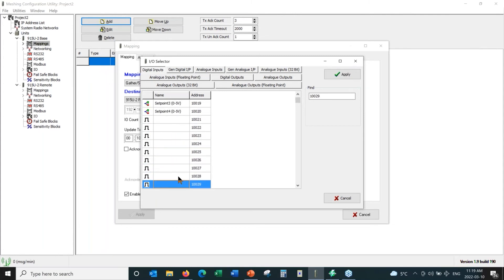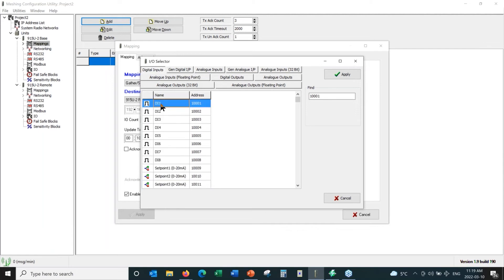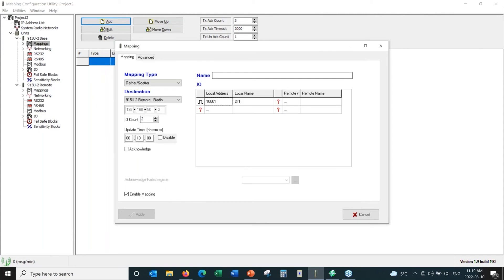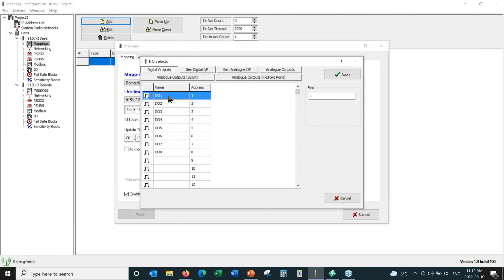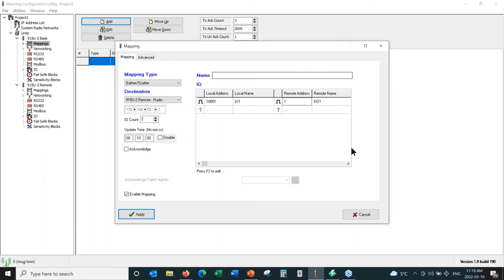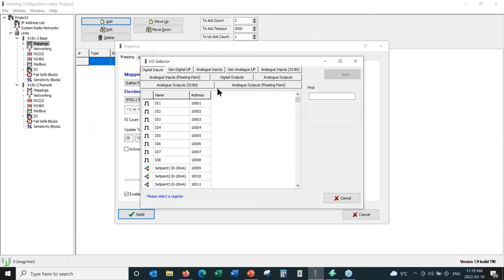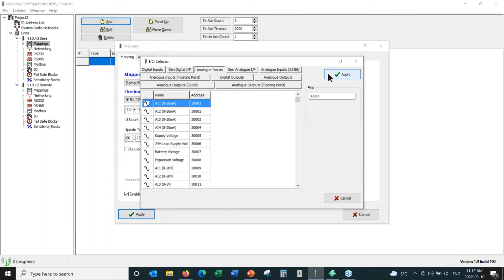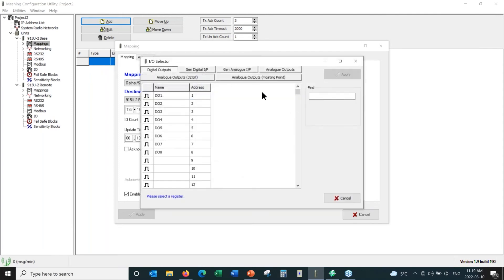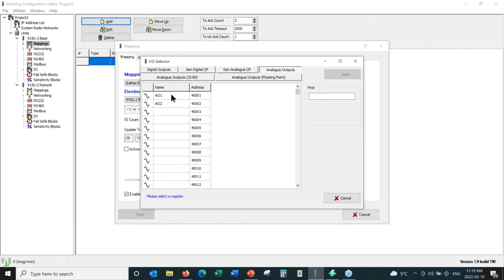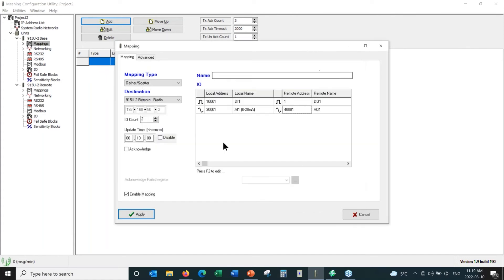For today, I'm going to grab digital input number one and send it to the remote radio's digital output number one, and hit Apply. Then we're going to take a 4-to-20 milliamp signal — we go to analog inputs, take analog input number one, hit Apply. For the remote address, we select analog outputs and send it to analog output number one. So I have a basic mapping: DI1 to DO1, and analog input one to analog output one, going from the base radio to the remote unit.